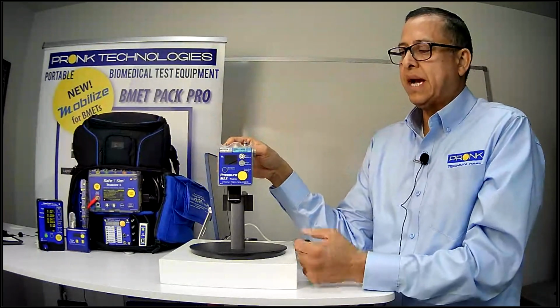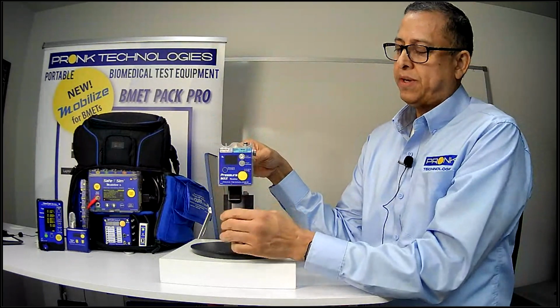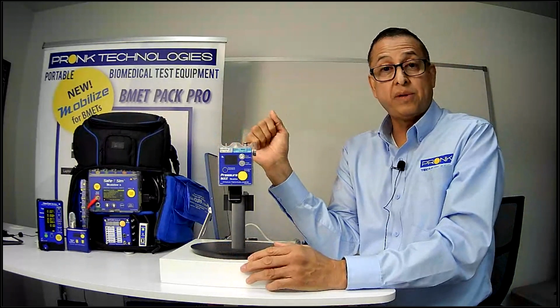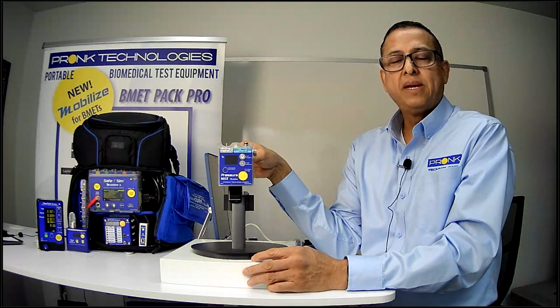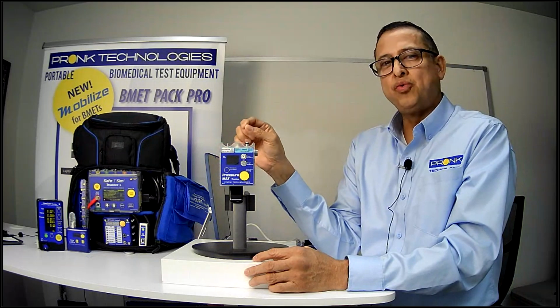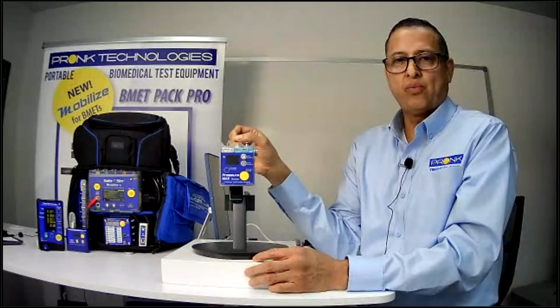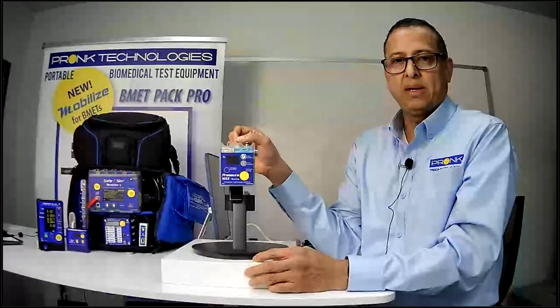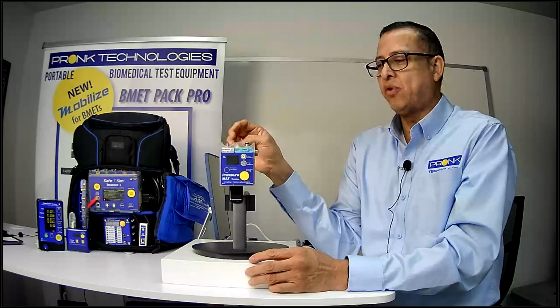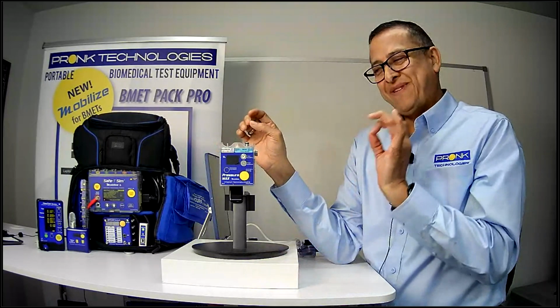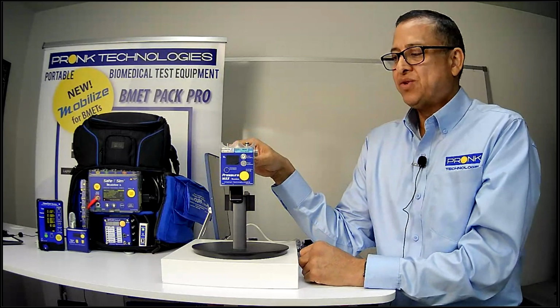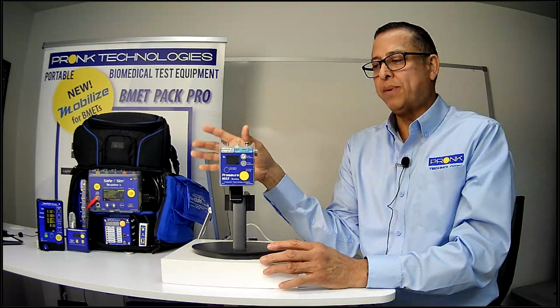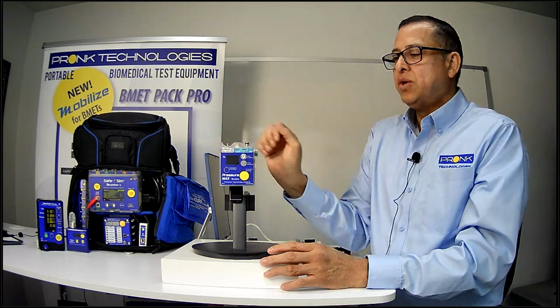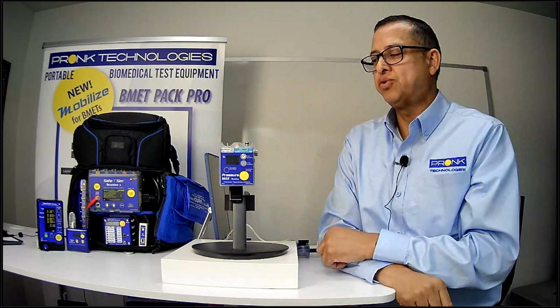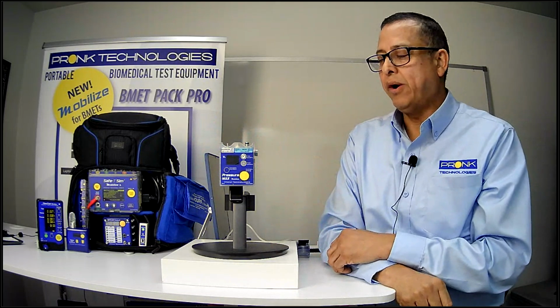But we also designed it with what we refer to as the narrow port, and that has a range of -300 to +400 millimeters of mercury, and that has an accuracy of up to 0.2% of the reading. So less than 1%, 0.2% of the reading, you can get each and every test point within that result, and so it provides very high precision readings. So you're not having to sacrifice performance by having a multi-channel device. You can get the accuracy that you need between those 2 ports very well.